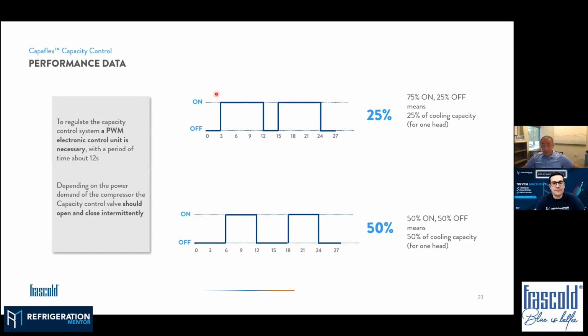So the remaining game is made by the controller, because we saw that when the valve is off, we are at full capacity, and when the valve is on, we are closing the suction side. So it means that on a period of 12 seconds, for example, if we are keeping 3 seconds off and the remaining on, we have 25% of the cooling capacity for that head, of course. And if we are doing, for example, like the example below, 6 seconds on, 6 seconds off, we'll have 50% of the flow for that head. So quite straightforward.